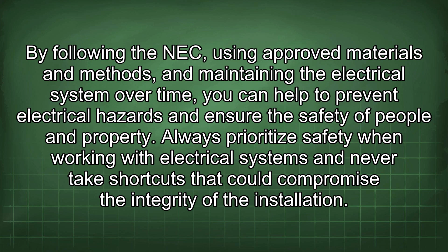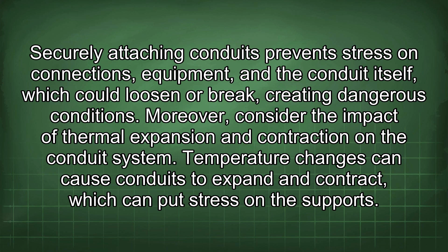Securely attaching conduits prevents stress on connections, equipment, and the conduit itself, which could loosen or break, creating dangerous conditions. Moreover, consider the impact of thermal expansion and contraction on the conduit system. Temperature changes can cause conduits to expand and contract, which can put stress on the supports.